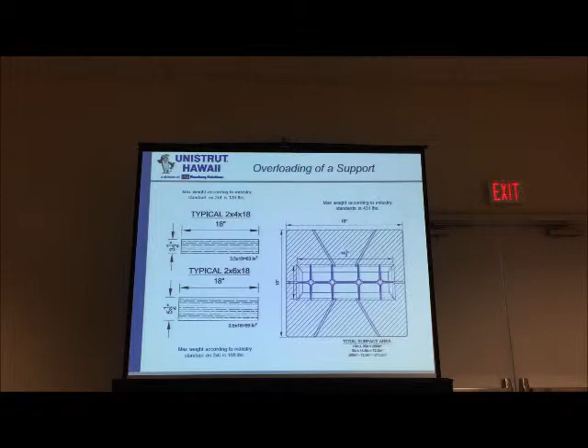Now there's a guide, you can look this up on the internet when you have piping, and what the piping weighs when it's empty and what the piping weighs when it's full of water. And so you can calculate what your support spacing needs to be depending on the number of pipes, the size, and having it filled with water. You know what the weights of those are going to be. And then you can calculate what size base am I going to need at what intervals, 5 feet, 6 feet, 10 feet, whatever it might be, and you can make your calculation as to how big this foot has to be in order to accommodate the service that you are providing on that system.